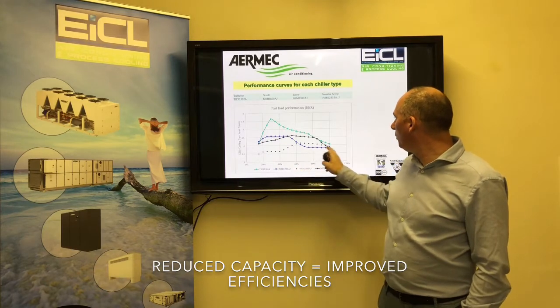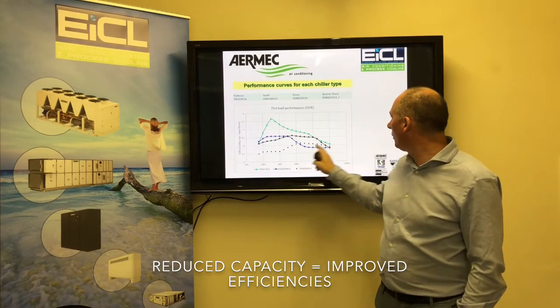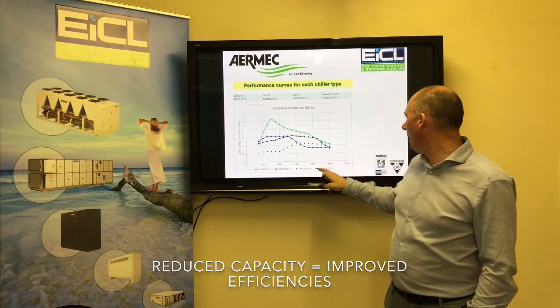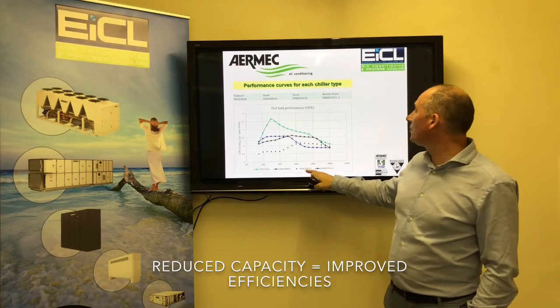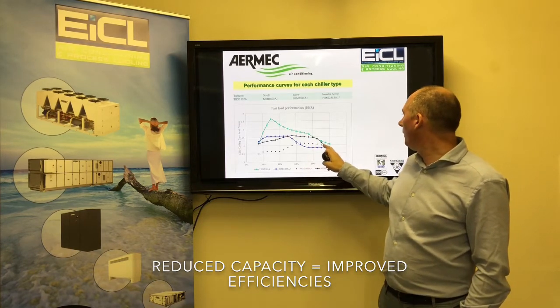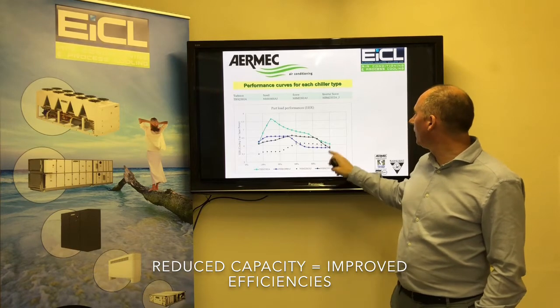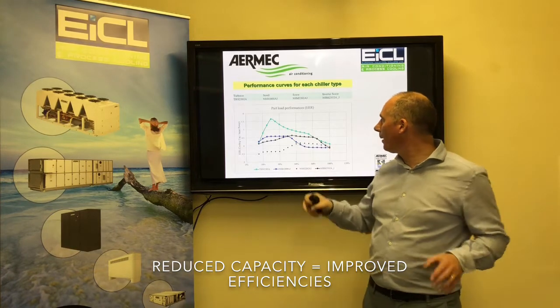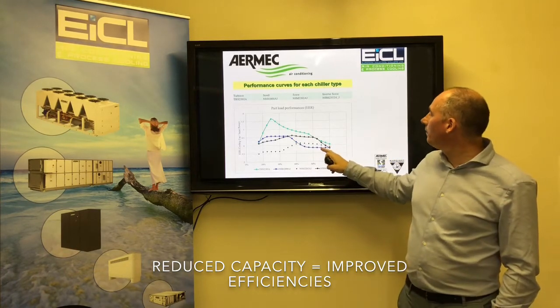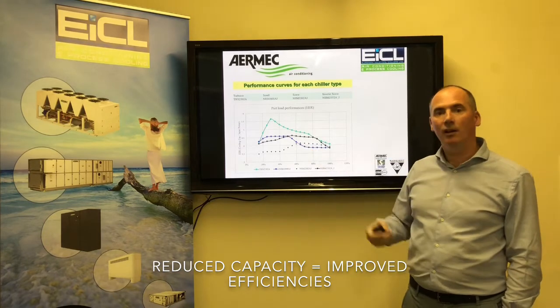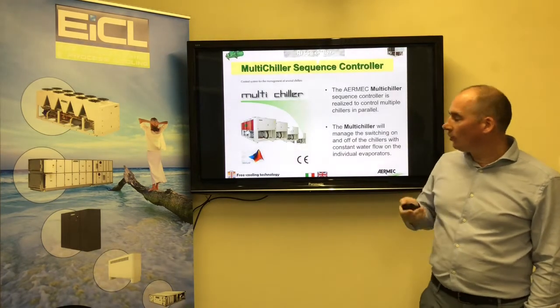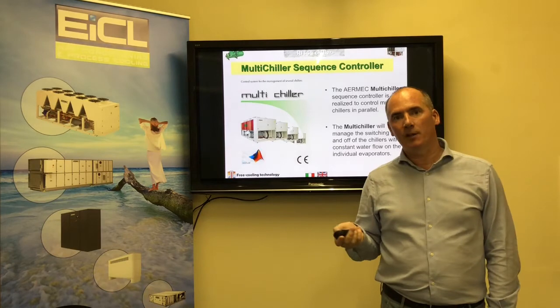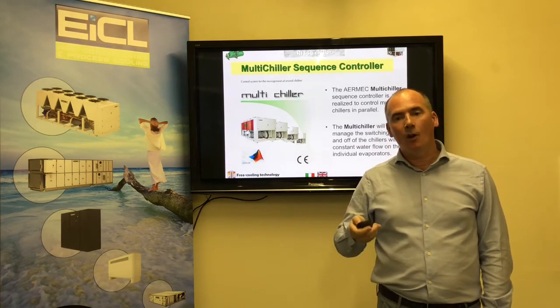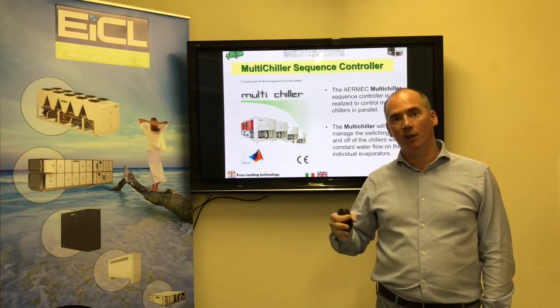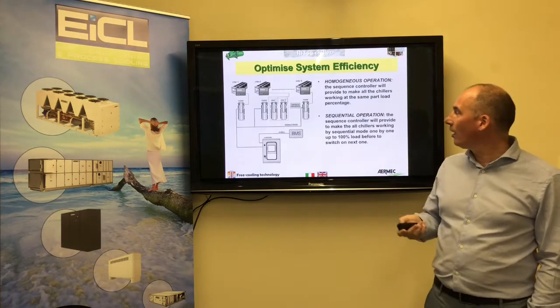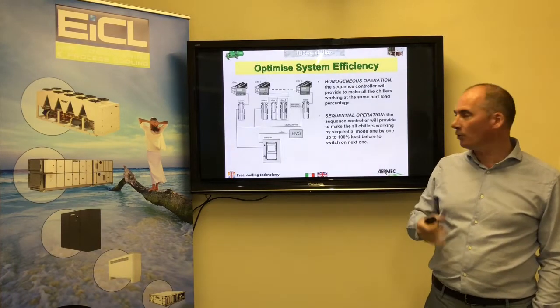So the NRB is the blue. The turbo core you'll see is the best. We have the NSM, which is the non-inverter screw, which is this one dotted here, and the inverter screw. So you can see how they overlap. But in general, the part load efficiency is better on the vast majority of them. So when we know that the part load efficiency is better, there's no sense really in running a chiller up to full load. We're better off running a multiple of chillers in part load.